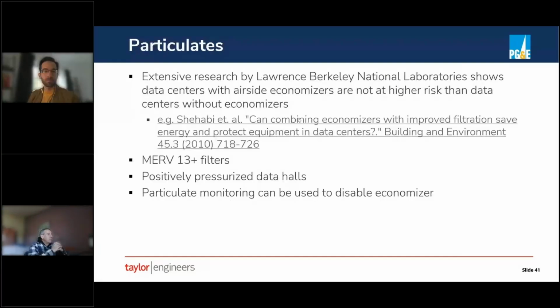So in addition to things like temperature and humidity, there are some other criteria I mentioned that need to be managed. One is particulates, cleanliness of the air, basically. There was a bunch of research that folks we know at Lawrence Berkeley Lab did that showed data centers with air economizers are not at higher risk than data centers without economizers. And so this was a big debate about 10, 15 years ago when this research was done: is it safe to use air economizers in data centers, or are you at risk of damaging the equipment because of the dirty air? And the research they found was as long as you have filtration that's MERV 13 or higher, you're not at much risk.